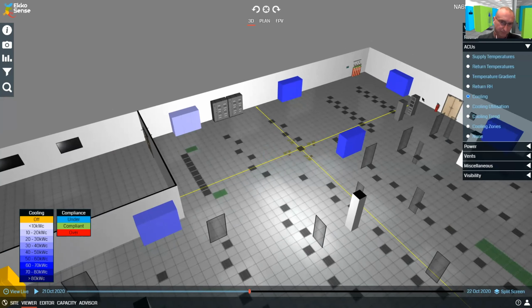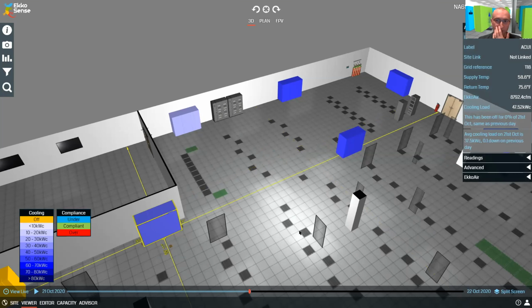One of the things we've done, as Martin alluded to earlier, is if you hover over an aircon unit, you can see the cooling duty it's using - 47.5 kilowatts here of cooling, along with return and supply. We have a piece of hardware that can be retrofit onto any device, whether DX cooling, chilled water cooling, large or small units, or in-row units. It monitors the cooling load and airflow across those units in real-time, essentially acting as a smart meter for kilowatts of cooling, so you can monitor how it's actually working.